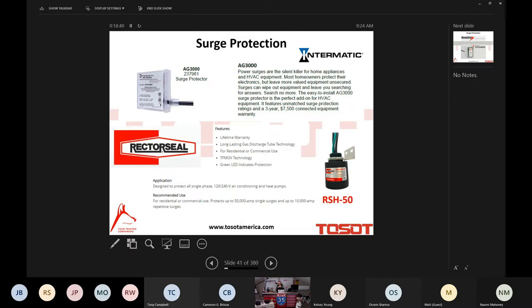An item which will net out to them for less than $100, probably substantially less than $100, can save them thousands of dollars in lost boards, lost equipment, and lost compressors. If that circuit were to take a surge, whether it be God-made in the form of lightning or man-made in the form of something internal to the grid, these items are sacrificial. And I have some examples of them here.